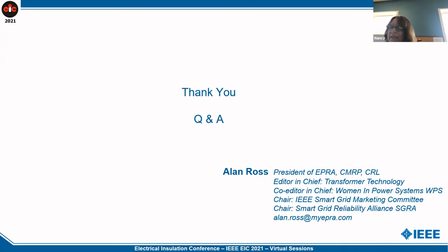It's not a red flag, but it's a yellow flag, and things are still working. I'm waiting for that catastrophic failure. So what are your thoughts on that? That's exactly your point—that's a weak transformer waiting for some form of anomaly to happen, and it's going to fail. If it were not a wet transformer, it could probably withstand that anomaly.